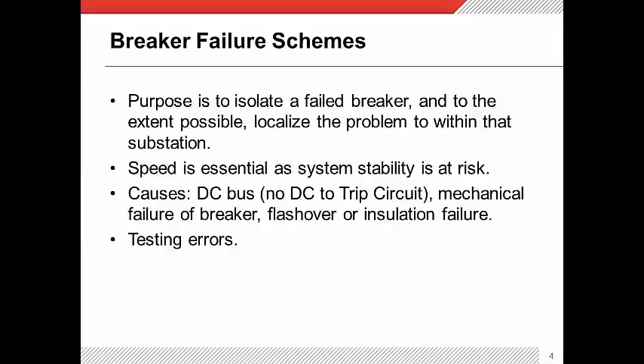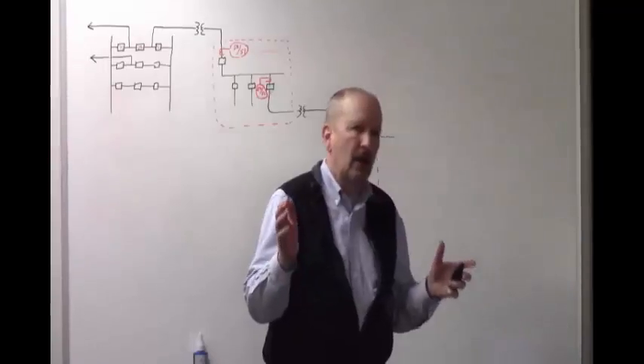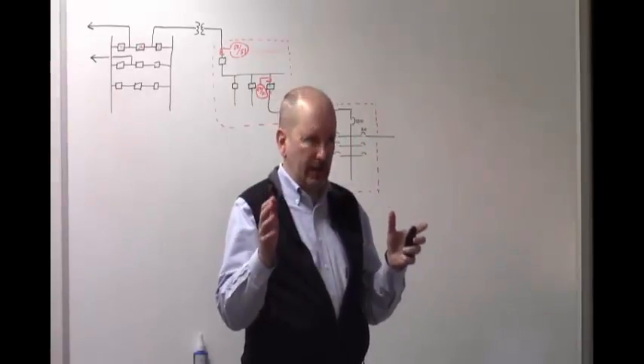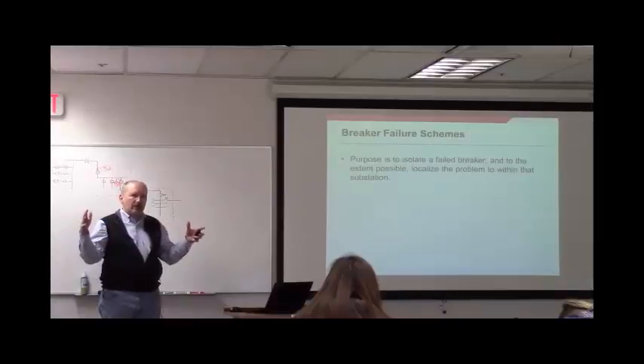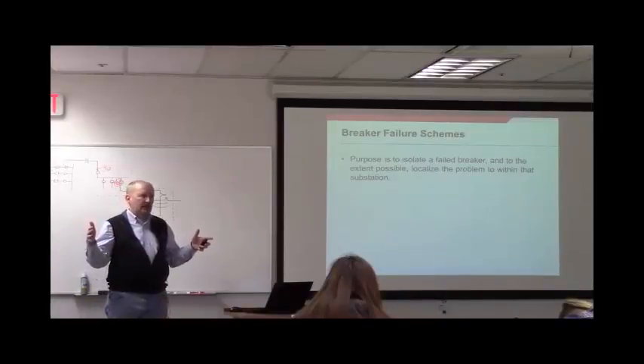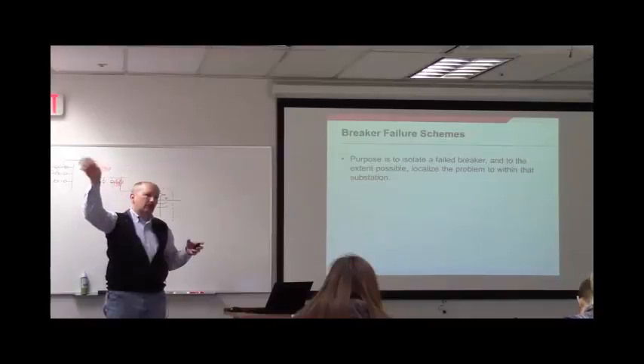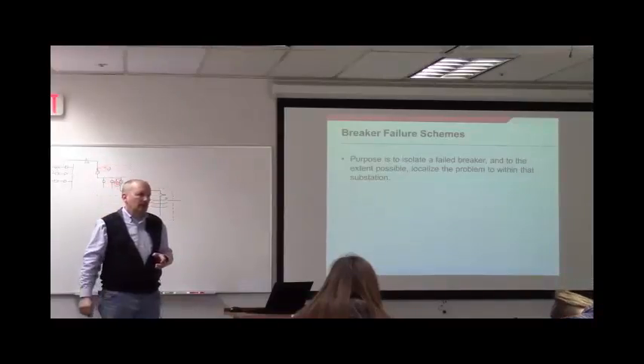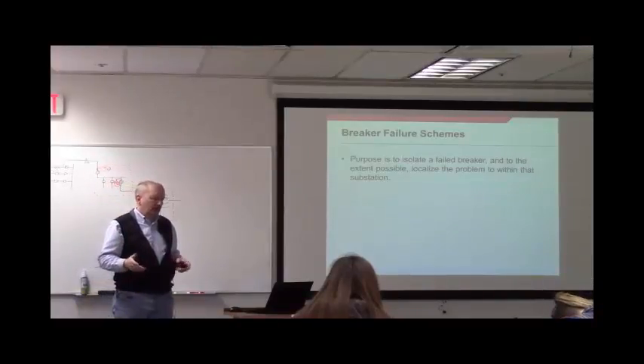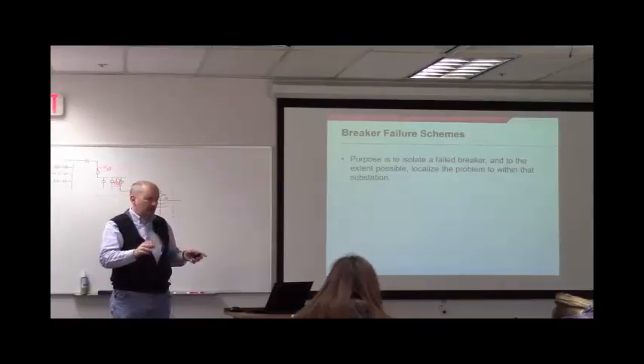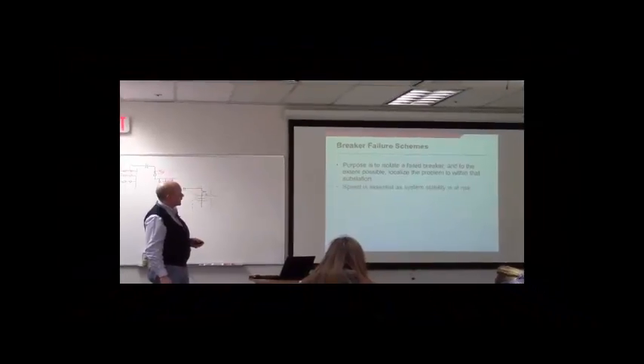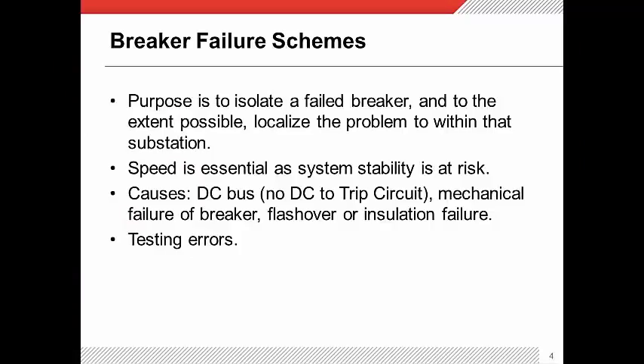The purpose of a breaker failure scheme is to, to the extent possible, isolate a failed breaker and contain that within the boundaries of the substation, so you're not having to trip circuit breakers remotely. That caveat — 'to the extent possible' — is a pretty important one. Speed is essential because the stability of the system is really at risk.